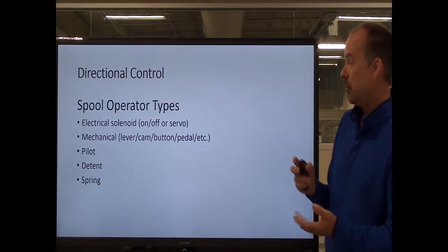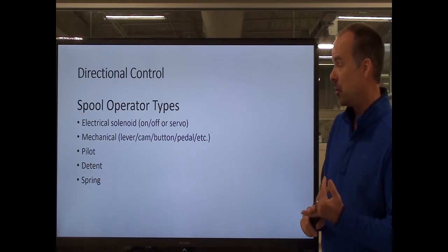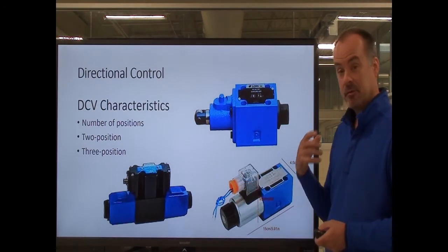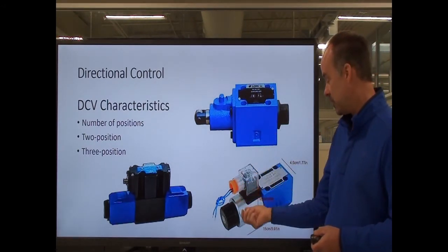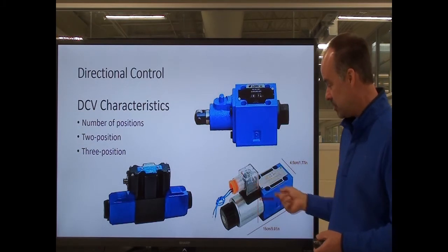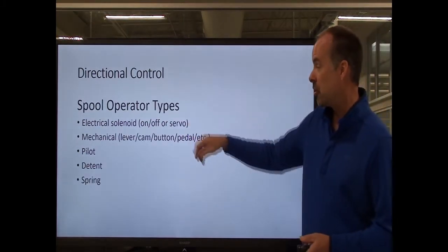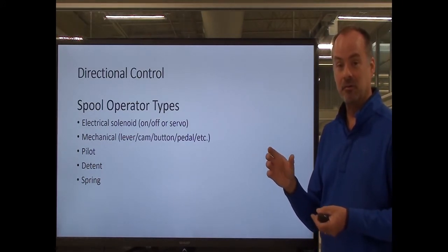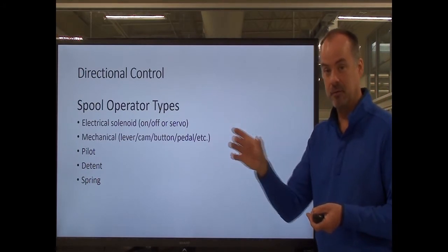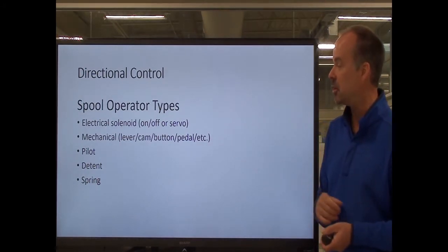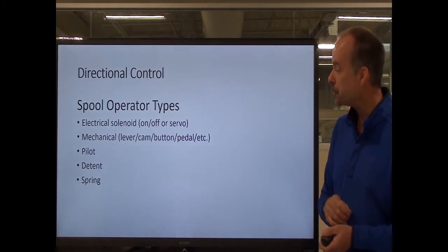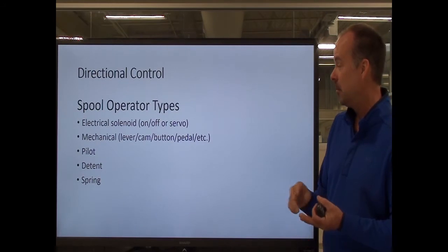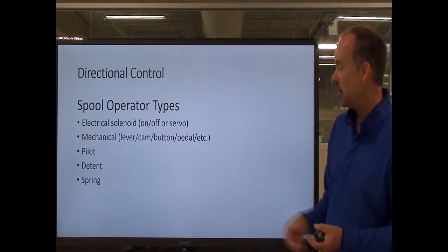Spool operators: you can have electrical solenoids — the valve is either on or off. Energize it and the spool shifts; de-energize it and the spool shifts back. Or it could be a servo, which allows an analog signal — it's not just on or off. You can shift the spool a little bit, a lot, or anywhere in between, giving you infinite adjustment on how far you shift that spool. It could also be a mechanical operator: a lever, a cam, a push button, or a pedal.